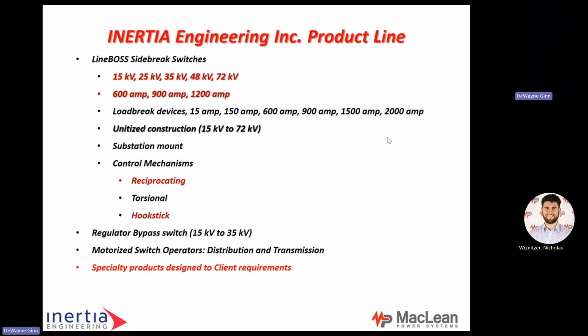So in the Inertia Engineering product line, everything is a side break switch. It's all copper construction, 15, 25, 35, 48, and 72 kV, 600, 900, 1200 amps. We want to go up to 1200 amps, but we don't go above that at all. Our load break devices are 15, 150, 600, 900, 1500, 2000 amps. So we make all those in-house. Everything is unitized construction, again, which allows for quick, easy installation on a pole. Also, it eliminates adjustments, so it really helps to do that.